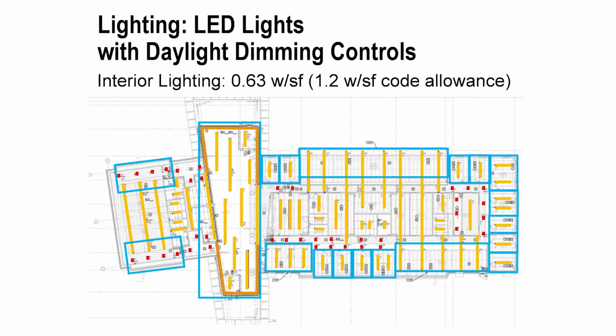On the lighting side, this building has LED lighting, but every building has that now, so that's not new. What's different is that we really took the time to design the light to hit the levels we needed without exceeding them. That let us get our lighting power density down to about half of what the code we designed to was recommending. So even with all lights on, we're saving significant energy.